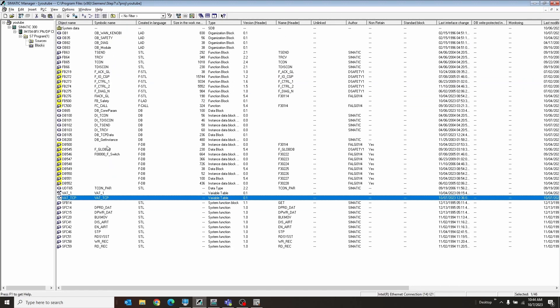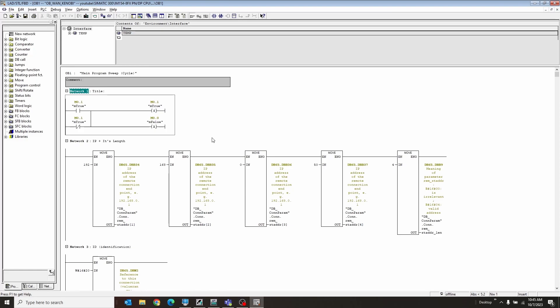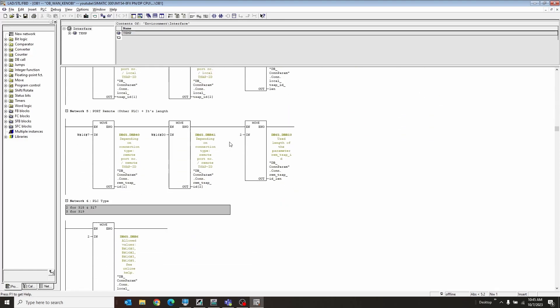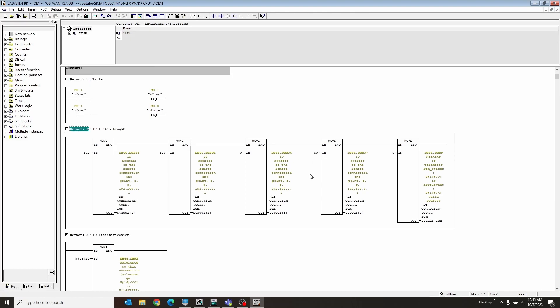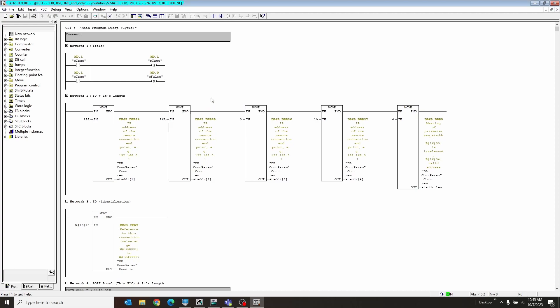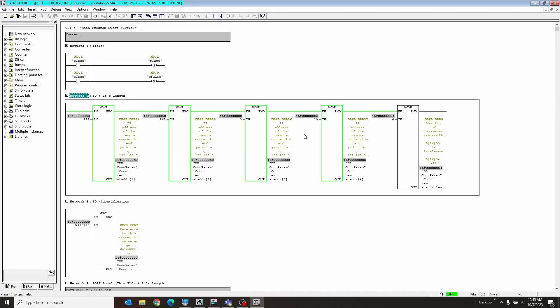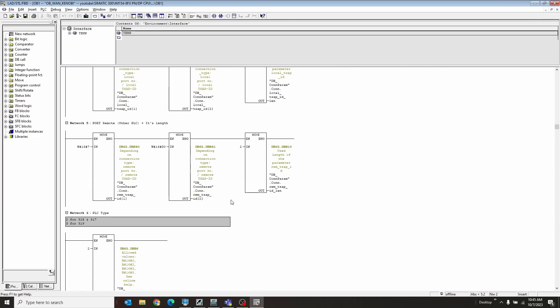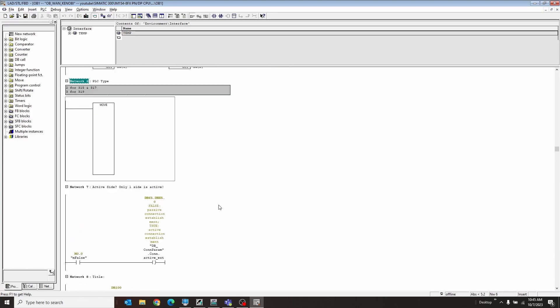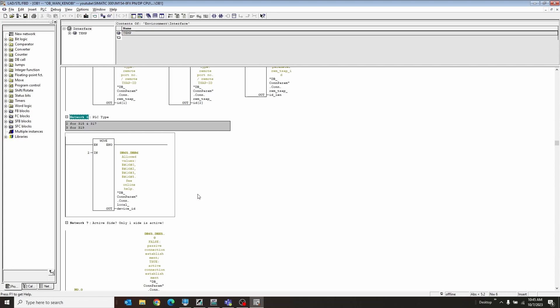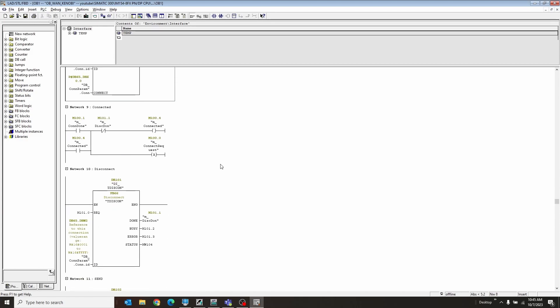This is all the same stuff, but it's mixed with a whole bunch of safety stuff as well, because this is a safety PLC. So if we go to his OB1, it's all the exact same code. The only difference is he is looking at a 50, which is our first PLC. This PLC we are on is 192.168.0.10. And he is looking at 50, the other PLC. In the first PLC, he is 50 and he is looking at 10. So that's our second PLC. So going back to the second PLC, hopefully I didn't make that too confusing. All the same logic going down. The ports are all the same. I only chose one port and they can talk together on that port. He is also a device type of two. Coming down here, we have turned off his active connection. And the rest of it is the exact same logic. So there we all go.